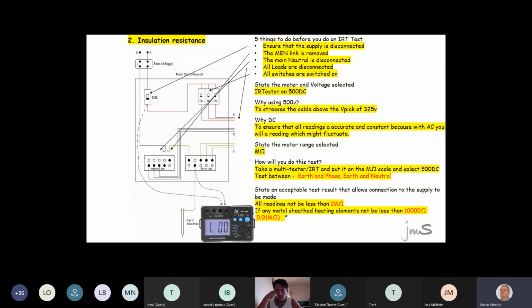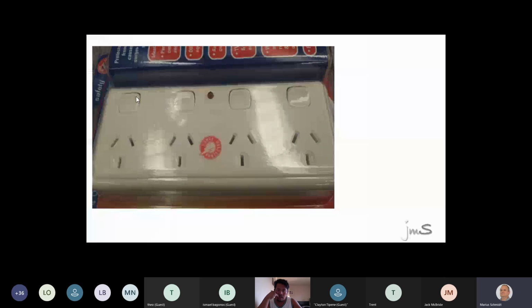Right, guys. Now, here comes a multi-million-dollar question. Why can't I use a 9-volt battery to do this test? Why can't I take an ohm meter and measure between earth and phase with a multimeter on the ohm scale? A, because the multimeter is too small, or B, it's not 500 volts. How many volts is the minimum we said? 325. Your multimeter might only have a 9-volt battery in it. Is that enough pressure? No. So it will not put a signal through from the one metal through the copper to the cable. It will not pick that up.